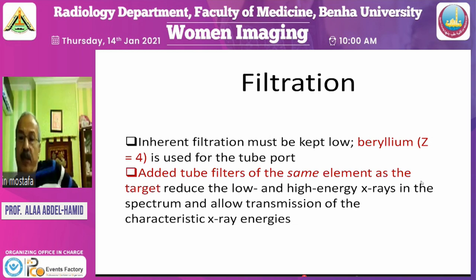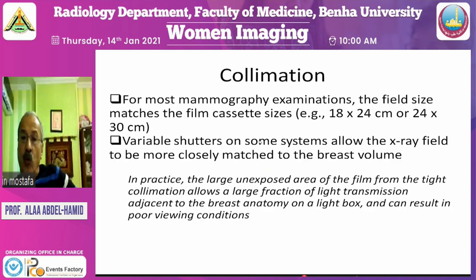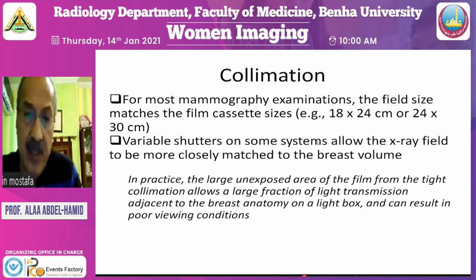Filtrations, we use different materials for filtrations, for example, the beryllium, and it's used for tube port, and the added tube filters here reduce the low and the high energy side of the X-ray beam, and then produce a more homogeneous X-ray beam than without using the filter. Collimation is very important in order to put the size of the field coinciding with the size of the film, that may be 18 by 24 centimeters or 24 by 30 centimeters.